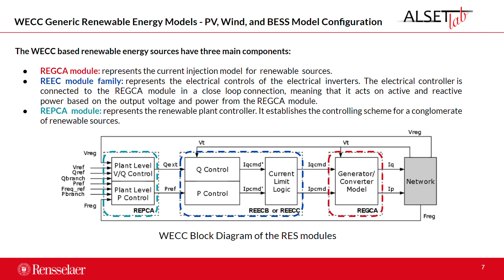The renewable energy sources are comprised of three main components. In red, we have the REGCA module, which represents the current injection model of the renewable sources. In blue, we have the REEC module family, which represents the electrical controls of the electrical inverters. And REPCA, which represents the renewable plant controller. These three modules combined represent the three sources: battery, PV, and wind.